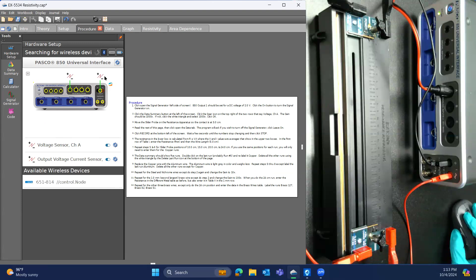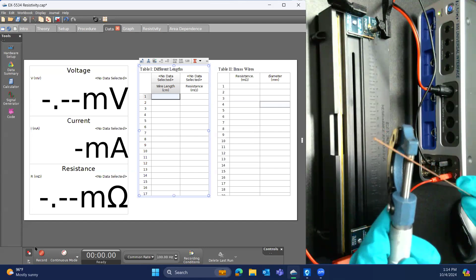So to start off, we're going to double check and make sure all of our connections are secure and made. And then we will go into the data page and we'll start collecting some data after we load our first wire sample in. So the procedure says start with copper. It really doesn't matter, but I'm going to follow the instructions and insert the copper. Now, it's recommended that you measure the diameter with a good pair of micrometers if you have access to one. If you don't, we have supplied the diameters on the setup page of the Capstone file.